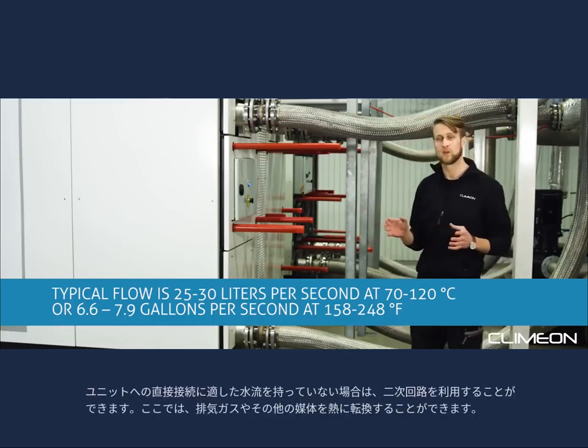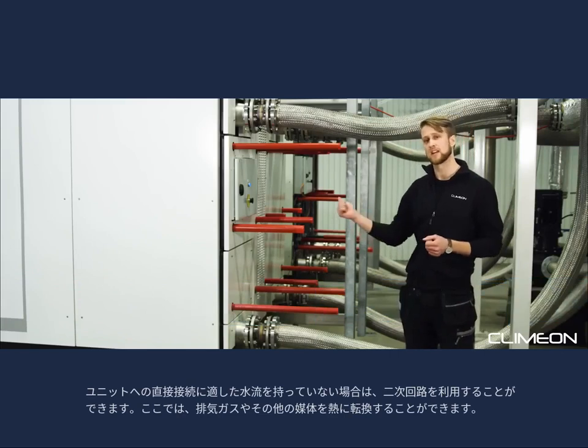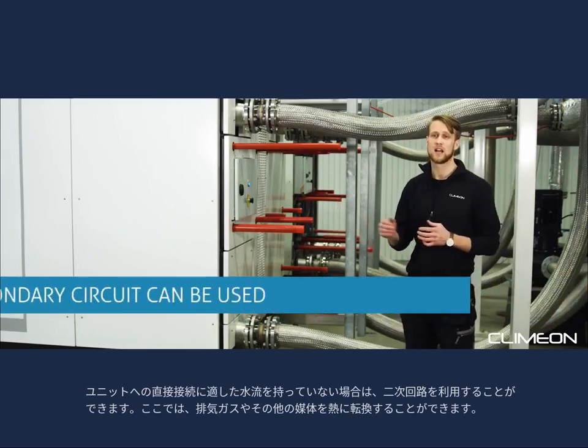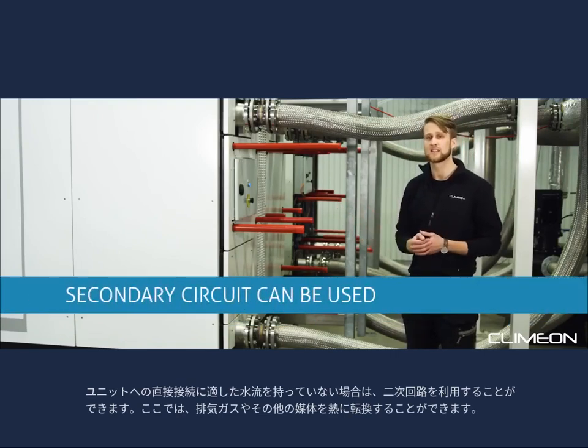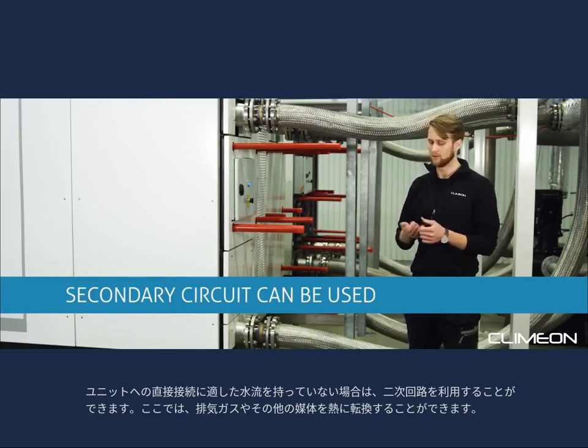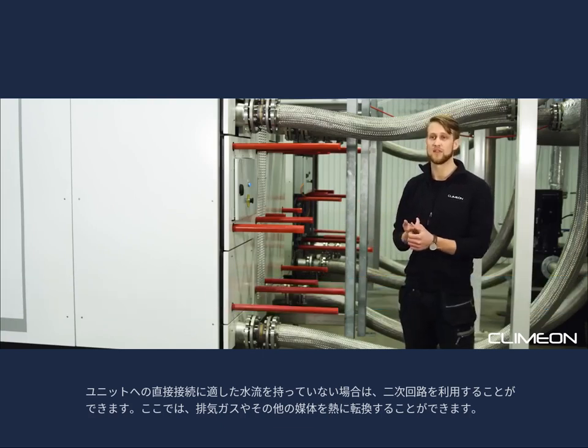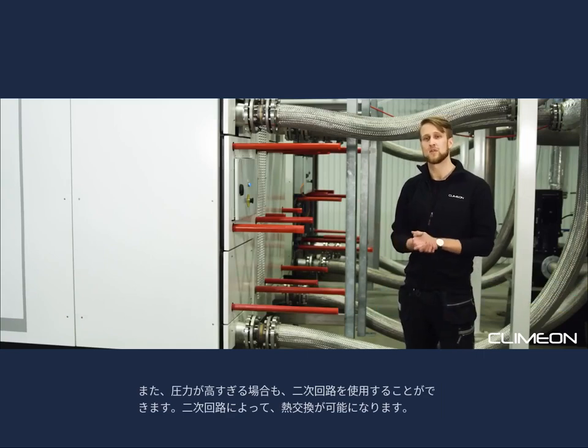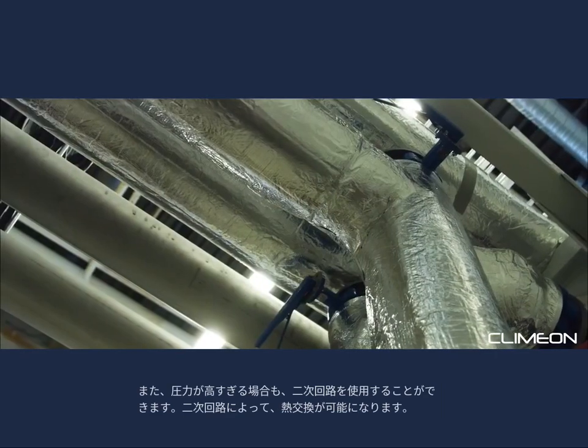If you don't have a water stream that is suitable for direct connection to the unit, you can always utilize a secondary circuit where you heat exchange heat from flue gases or any other type of media. And also, if the pressure is too high in your water stream, you could also use a secondary circuit to heat exchange the media to the water.